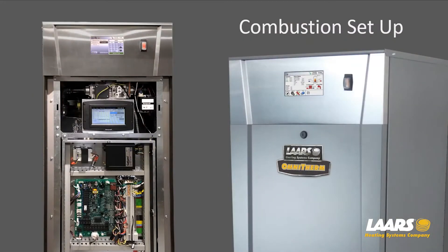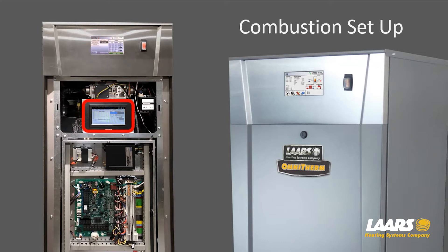The Omni Therm uses two displays for combustion setup. The link display would be used to increase your set point to keep the boiler running longer, and also to choose fan speeds or RPM so we can check combustion at multiple points. We also have a gas valve display, which is located under the lower cover door.